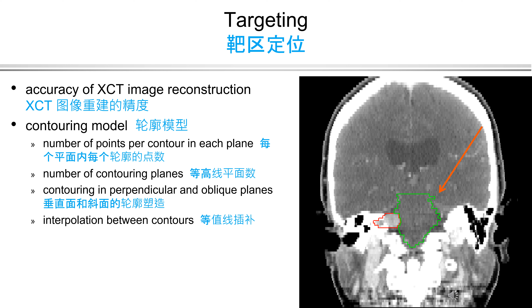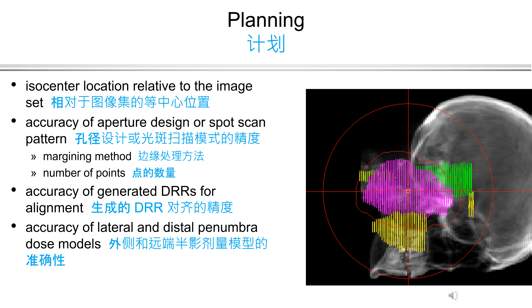There are many uncertainties associated with the planning of a treatment, a few of which are listed here. The first is the location of the isocenter relative to the image set. The second is the accuracy of the aperture design or spot scan pattern that places the field edge. This can be dependent upon the margining method and, for an aperture, the number of points in the projected aperture contour. The third is the accuracy of digitally reconstructed radiographs that are critical for aligning the patient with the treatment portal. Lastly, the accuracy of both the lateral and distal penumbra dose models can affect the applied margins and doses delivered to target and normal tissues.